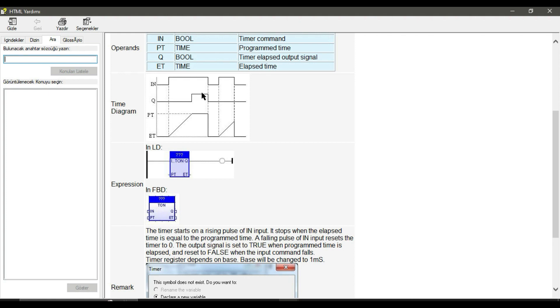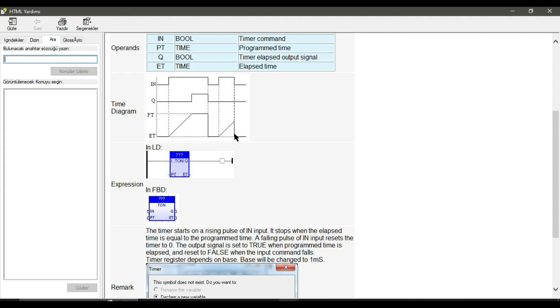As soon as the input becomes deactivated, the output will also become deactivated and the elapsed time will reset to zero. Note that if the elapsed time doesn't reach the preset time before the input becomes deactivated, the output never turns on, because as soon as the input becomes deactivated the elapsed time collapses to zero.